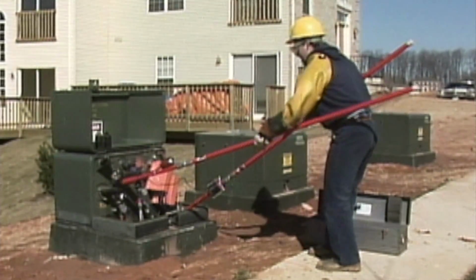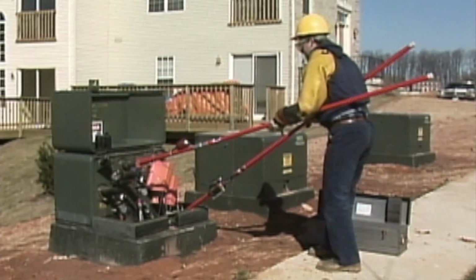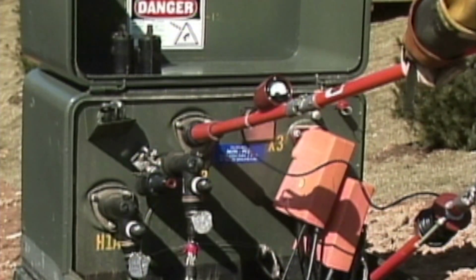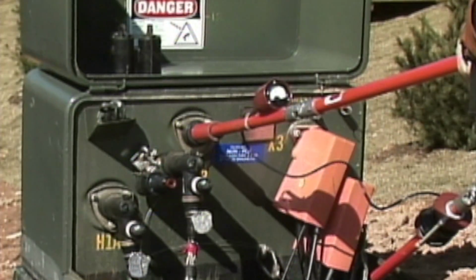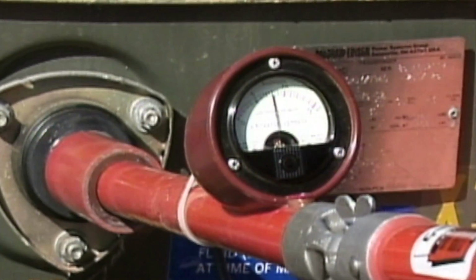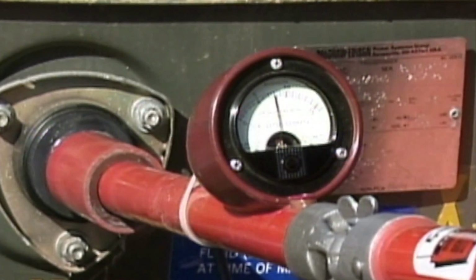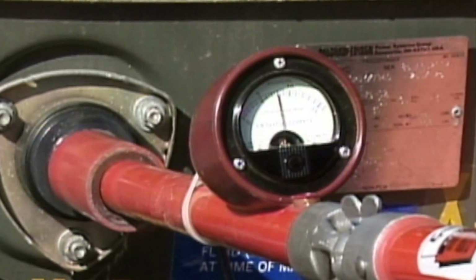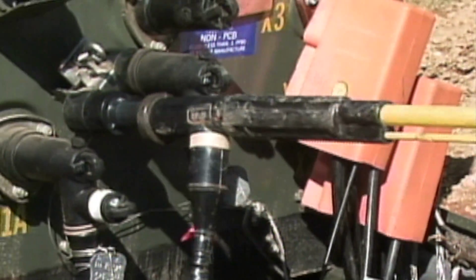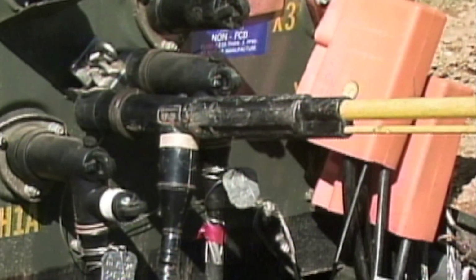After the test, he takes another reading between the energized bushing and ground to make sure that the meter is still functioning properly. The meter indicates a normal phase to ground voltage, which confirms its operation. Now he goes on to ground the cable.